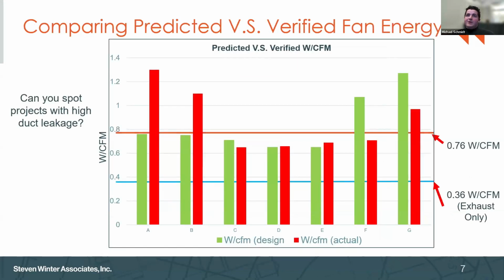Here is another graphic to show a few predicted values. This is all in the metric of watts per CFM of the ERV units in this case, versus the verified fan energy that we were actually finding on site. And I've set a few baselines on the graphic here. You'll remember the 0.76 watts per CFM bar that we talked about earlier as a recommendation. And below that, exhaust only that we've studied on large buildings shakes out to be about 0.36 watts per CFM. So folks that are coming from typically code-built construction to passive house, right? They are seeing an increase in fan energy.